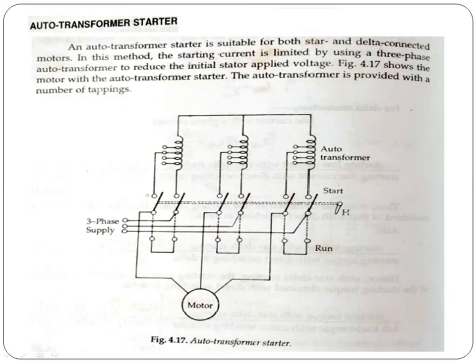This figure shows the motor with an autotransformer starter, and the autotransformer is provided with a number of tappings. So this is our auto transformer, and these are the tappings used, and in whatever position of tapping we connect our motor, that amount of voltage will be supplied to our three-phase induction motor. So due to that, we can get a lesser amount of voltage using the auto transformer starter.